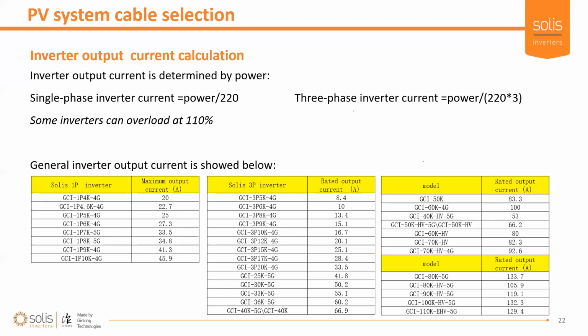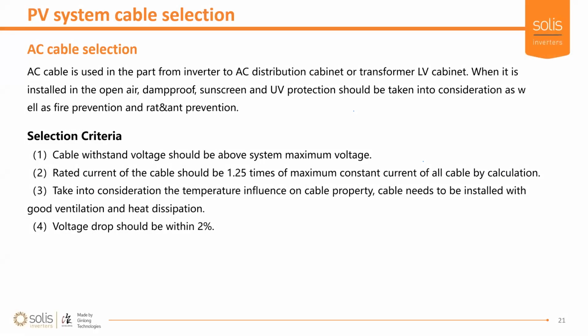Now again, this is a rule of thumb. You multiply that number by 1.25, shown in the previous slides. And the reason for this is clear. We definitely do not want our circuit breakers to trip. And as we know, we always design our circuit breakers to protect our cables. So the circuit breaker has to trip before the maximum current of the cable is reached.